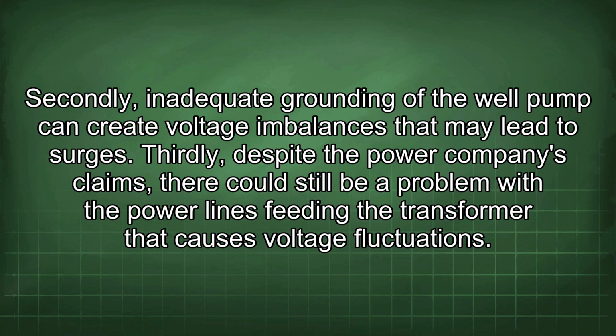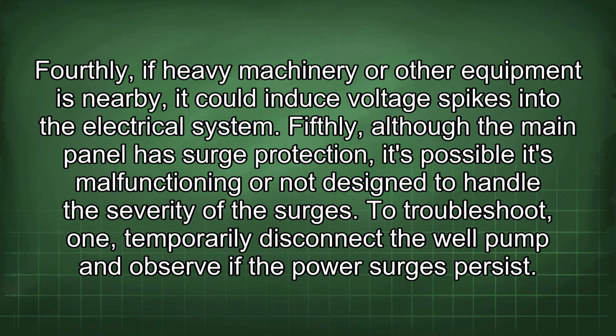Thirdly, despite the power company's claims, there could still be a problem with the power lines feeding the transformer that causes voltage fluctuations. Fourthly, if heavy machinery or other equipment is nearby, it could induce voltage spikes into the electrical system. Fifthly, although the main panel has surge protection, it's possible it's malfunctioning or not designed to handle the severity of the surges.